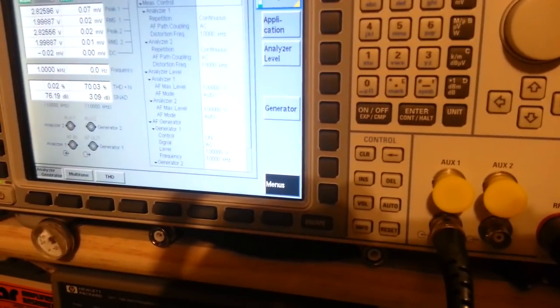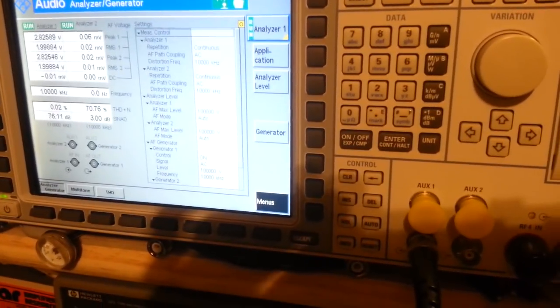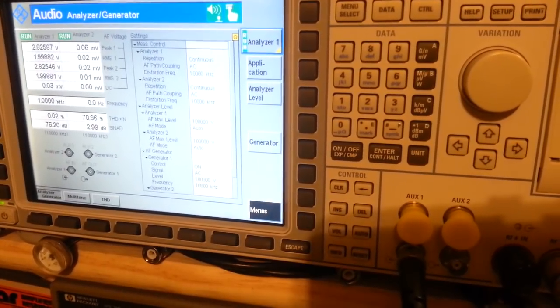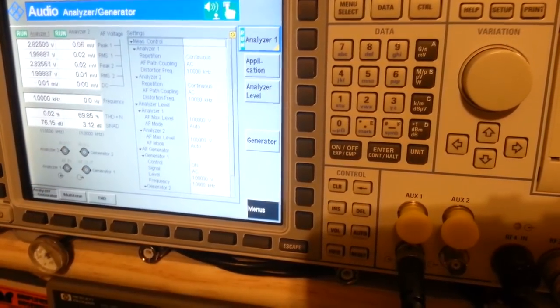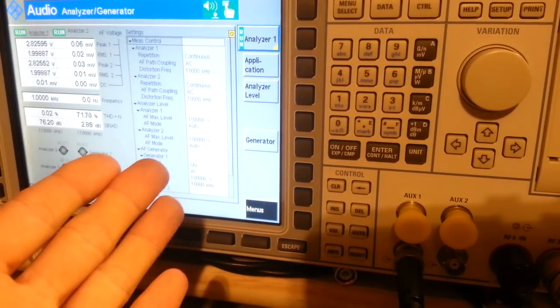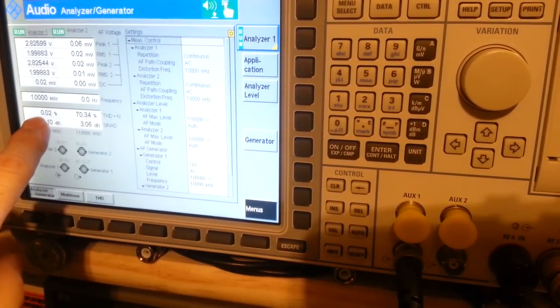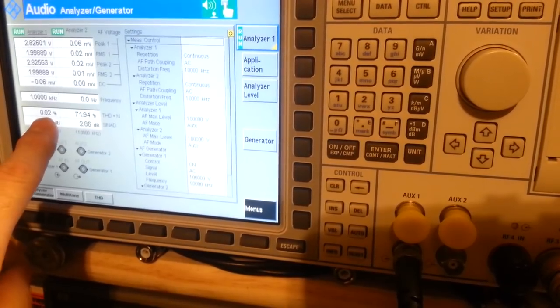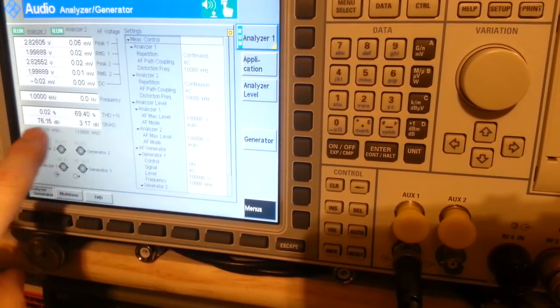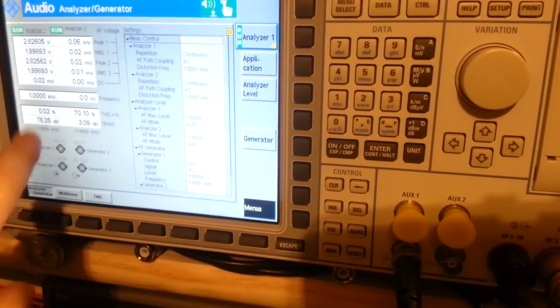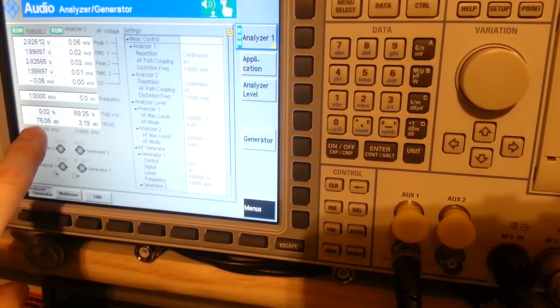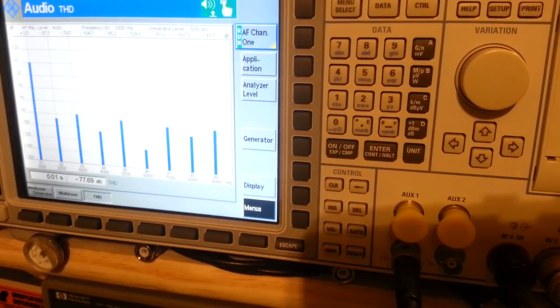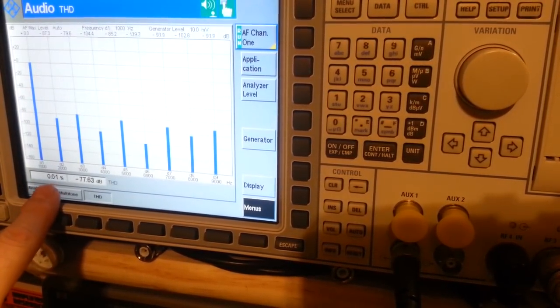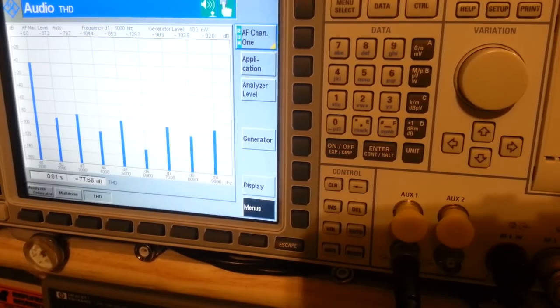And we come back over here and we can see it's not as good. And that's exactly what I would expect. You're comparing the Cadillac Rohde and Schwarz to the Rigol. It's not like it's bad, but the Rigol is nowhere close to the quality of something like this, and you can see that here. Our THD has gone up. It hasn't gone up much, but it has gone up to 0.02%. You can see our SINAD has dropped off considerably. It's now down in the 70s, around 76 dB SINAD. And THD is now a steady 0.01% instead of pretty much staying at 0.00% and only occasionally fluctuating to 0.01.